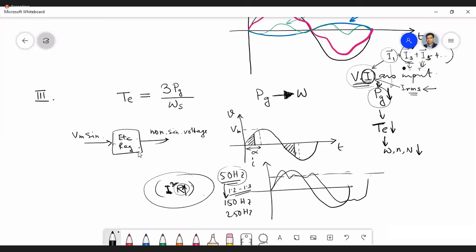So when you know at the design stage that your motor will be used with some power electronic drives, certainly there will be some sort of harmonics. Then you have to take into consideration this elevated loss. Okay, you have to consider some excess loss which will be there when this motor will be used with the power electronic drives.